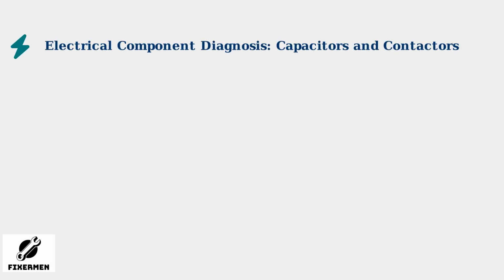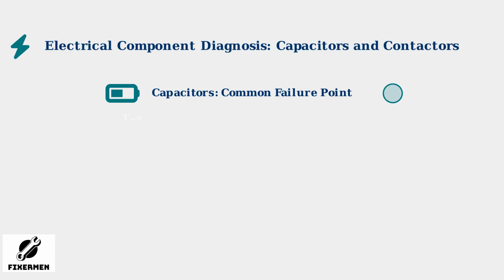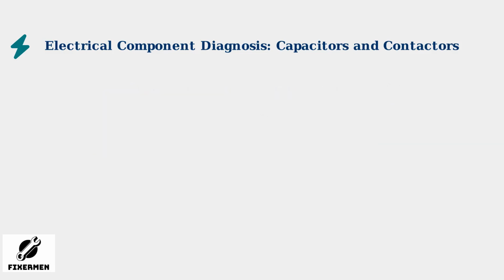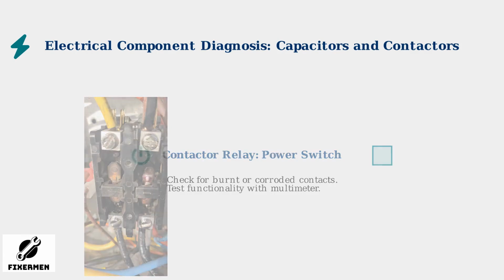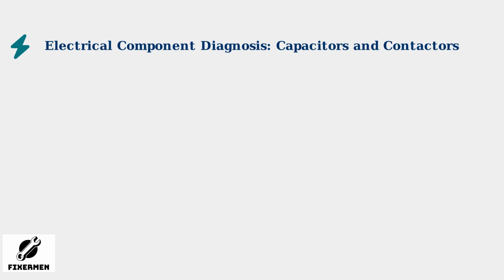If basic checks don't reveal the problem, focus on electrical components. Capacitors are a common failure point. Use a multimeter to test their capacitance. A reading significantly below the rated value indicates a need for replacement. Check the contactor relay, which switches power to the compressor. Look for burnt or corroded contacts, and test its functionality with a multimeter. Remember to disconnect power before any electrical testing to avoid shock.